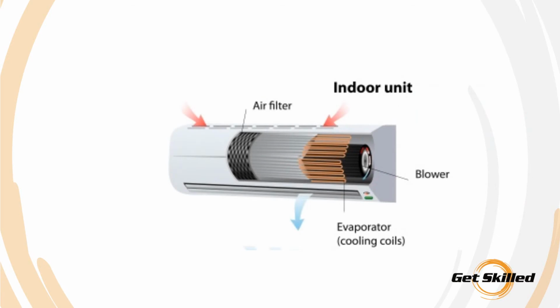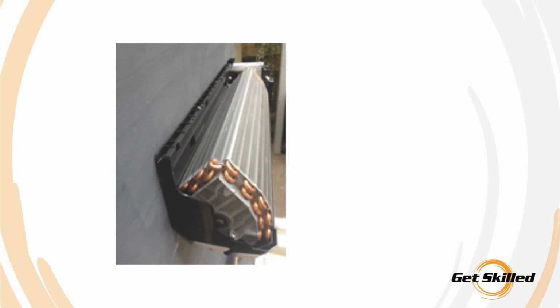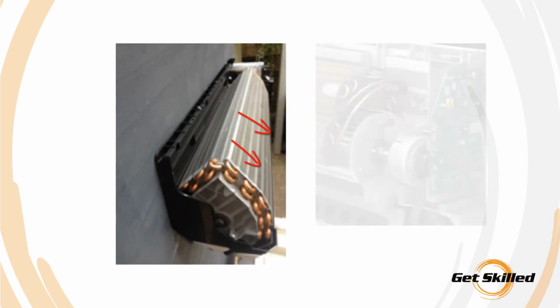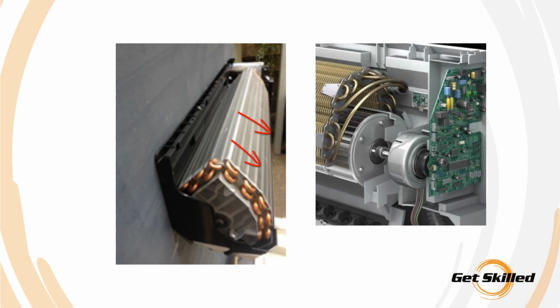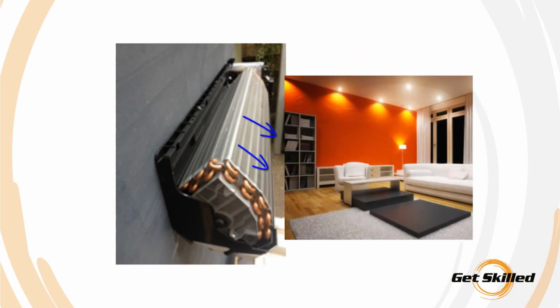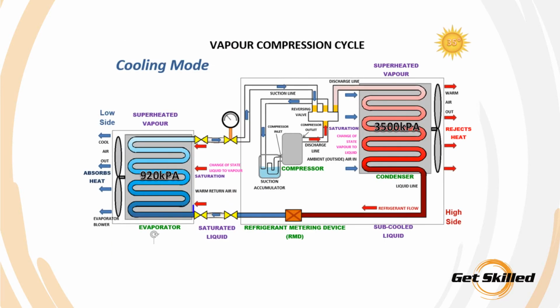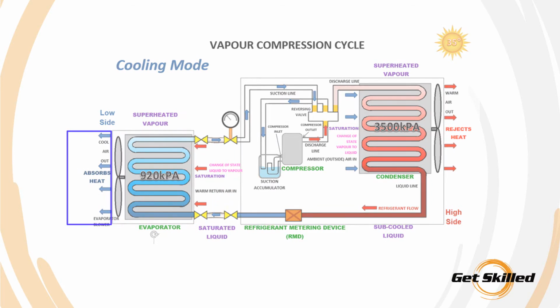The evaporator is where the heat is absorbed into the refrigeration system. The warm air is pulled into the evaporator and over the coils by a drum fan located in the evaporator, which is then used to blow the now cool air into the room. The refrigerant enters the evaporator in a low pressure liquid state and is vaporized or boiled by absorbing heat from the warm air flowing over the coils in the evaporator.